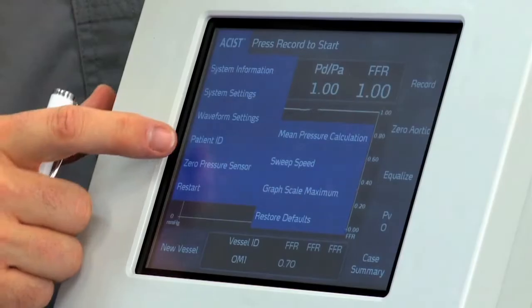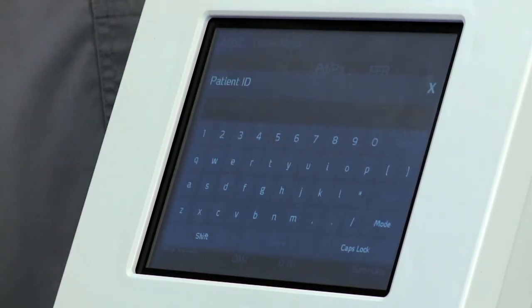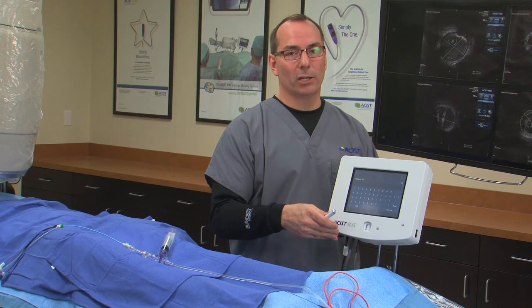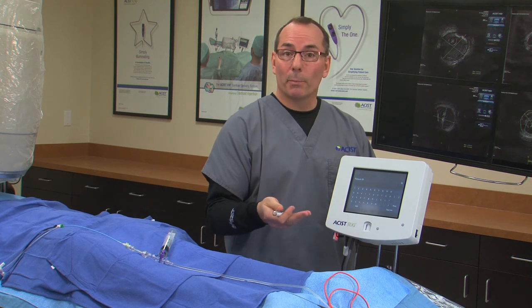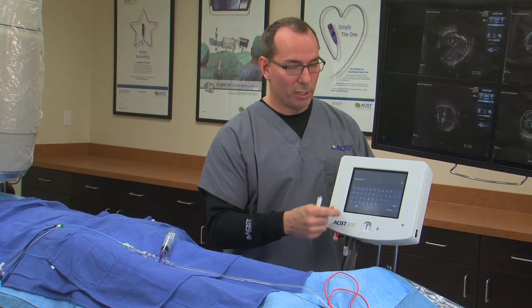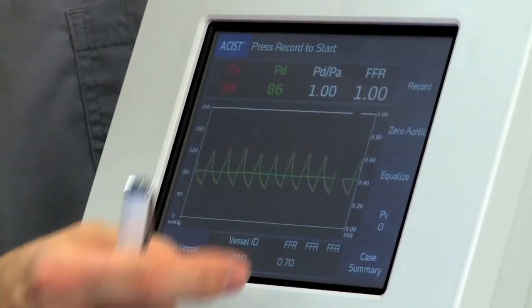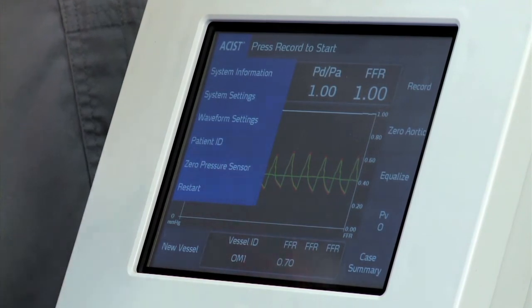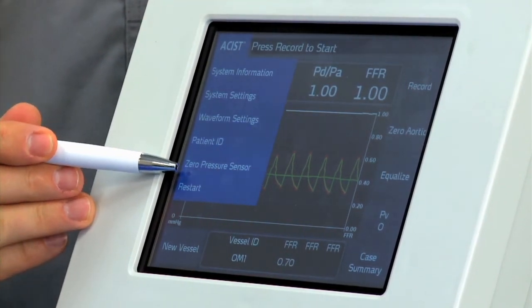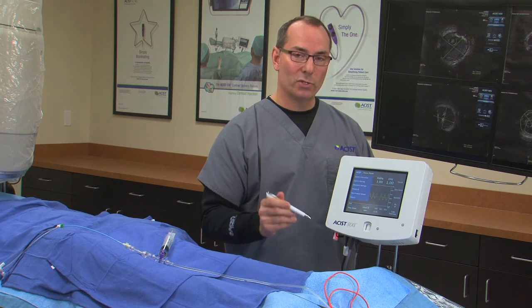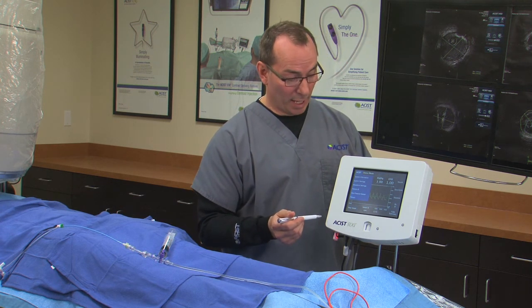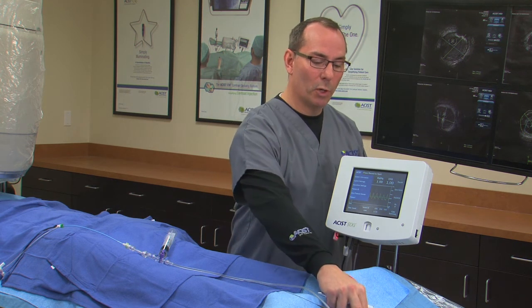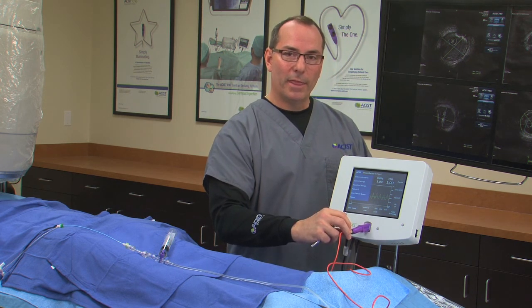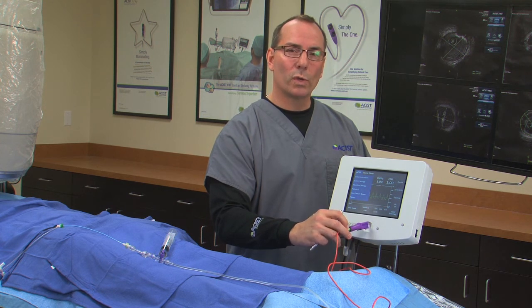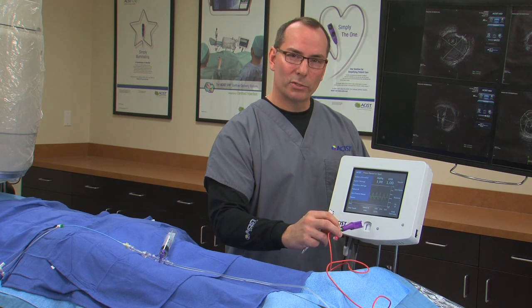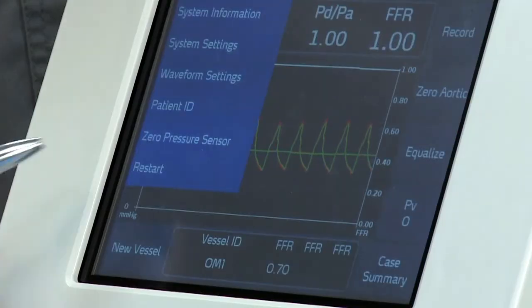Under our main drop-down menu, we also have Patient ID. So if you choose to, you can put a patient identifier, either an MR number or the patient's name or perhaps their initials in here, which will be tracked with that FFR. Zero pressure sensor, we have that capability, but if we're going to hit this, we have to make sure that pressure sensor is outside of the body when we recalibrate it. You notice when we plugged in our purple connector into the front of the unit that it's self-calibrated. There should really be no reason to do other zeroing of the pressure sensor, but if the physician chooses to, he would do that right here.